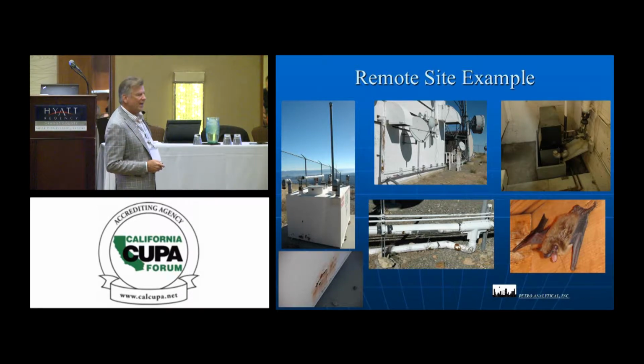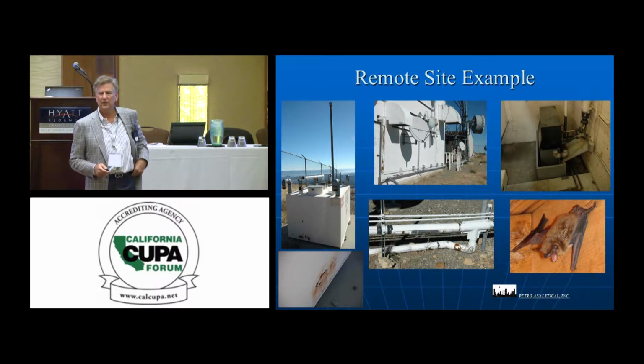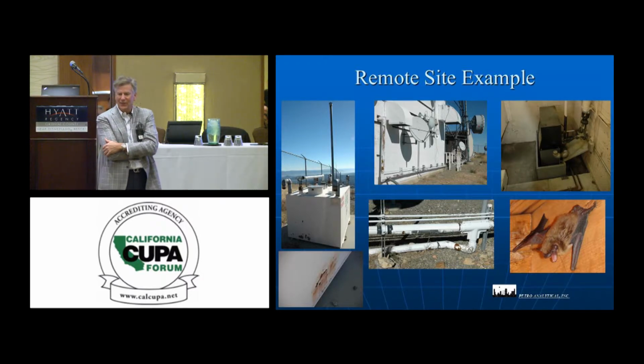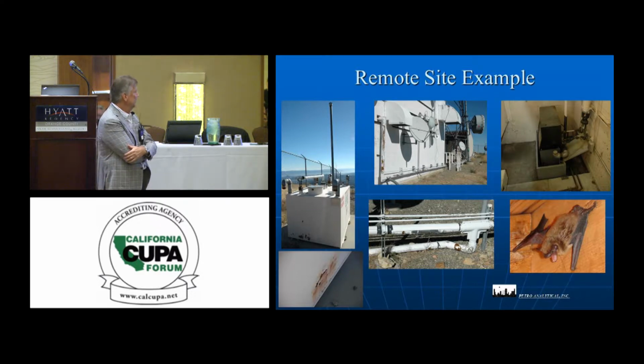So the bats and the rats and everyone else got in and chewed up all the nylon and the coating outside of the wiring in the day tank. So we have risks in emergency generators that even a card lock that is unmanned doesn't have, because they're built like a gas station. And the designers of these places, you know, they don't think about all this stuff. We come in after, and so we have to think about this. So we're going to redo this entire site.